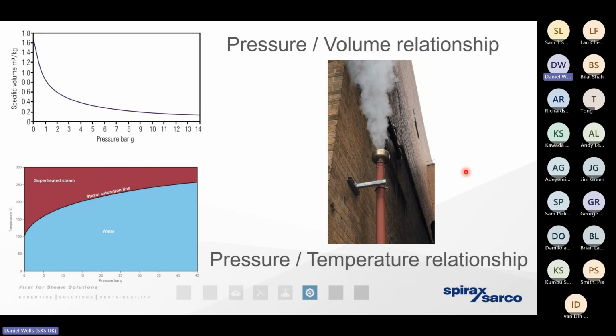Because we need the pressure drop across the steam trap, we need a positive pressure on the steam side that's pushing the condensate away to the lower side downstream of the trap. It tells us that if that trap were to fail in the open position, the effect of that steam as it depressurizes and expands significantly means that we've got to vent it away from the condensate infrastructure, because if we don't, we're going to experience a significant amount of damage. And similarly, any high temperature, high pressure, high energy condensate that exists upstream of the steam trap, that too could depressurize from a very high temperature to a much lower pressure where it can only exist at a lower temperature.